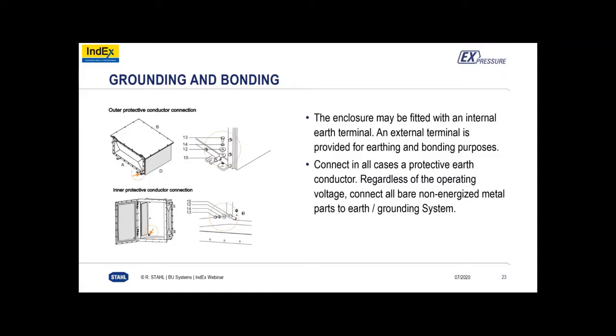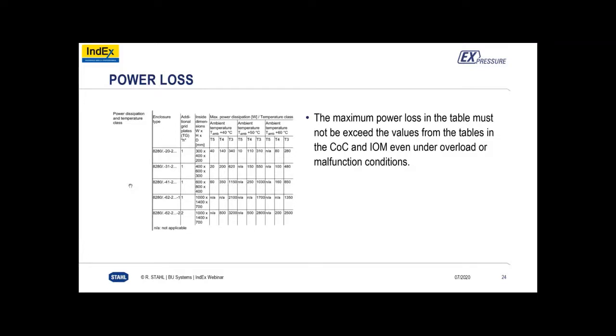So obviously earthing and bonding, that's the most important electrical safety feature there is. Lightning protection, sparks, stopping line-to-line shorts, ground faults, any injuries to people. So it has that external earth. So it's typical, like any EXD box. Now the maximum power loss in the table must not be exceeded. Once again, this information is found in the certificate of conformity, whether it be the IECEx or ATEX, and in the IOMs, installation, operation, and maintenance manuals. Depending on the ambient temperature, the T rating of your enclosure will change, also dependent on the size and the overall wattage dissipation.